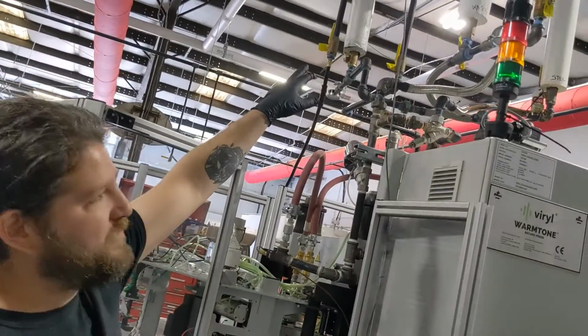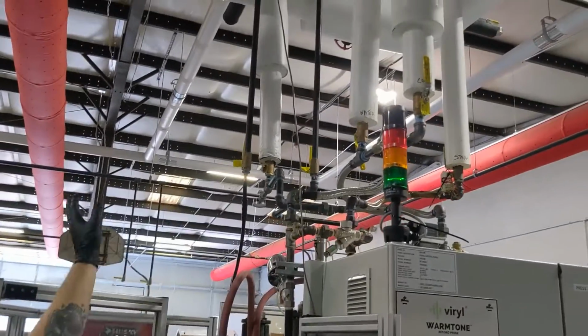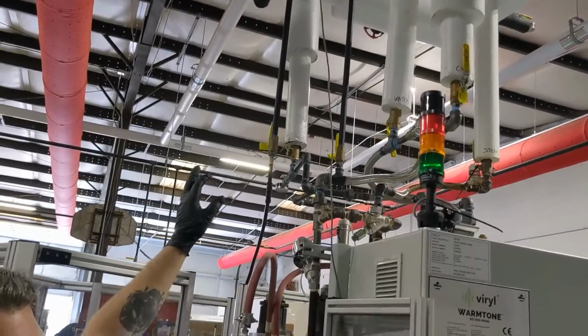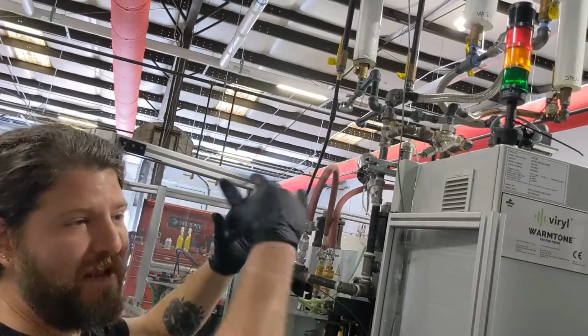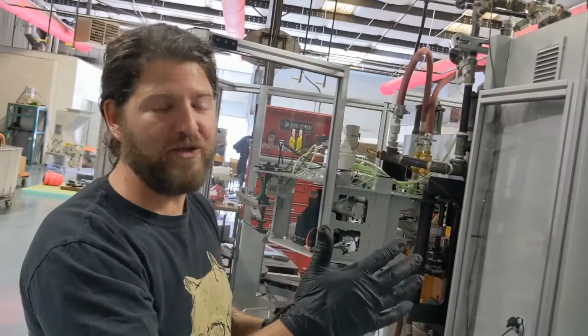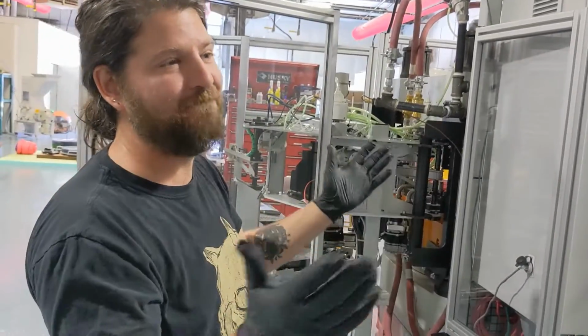If that globe valve is completely open, water is flowing at 120 PSI into that return line, which is too high because water can't get out. Think of it like merging traffic - if everyone on the highway is going 120 and you're trying to get on going 60, it's not going to work.